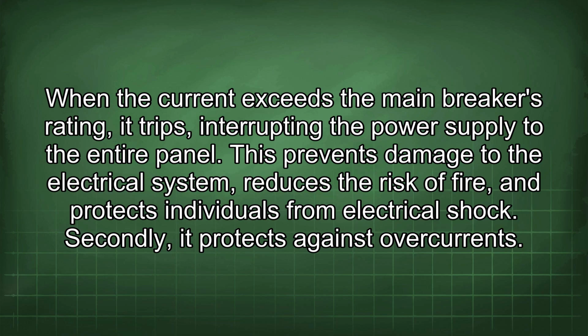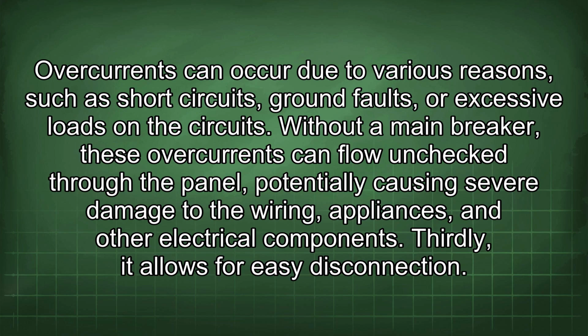Secondly, it protects against overcurrents. Overcurrents can occur due to various reasons, such as short circuits, ground faults, or excessive loads on the circuits. Without a main breaker, these overcurrents can flow unchecked through the panel, potentially causing severe damage to the wiring, appliances, and other electrical components. Thirdly, it allows for easy disconnection.